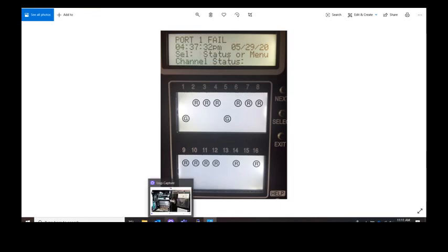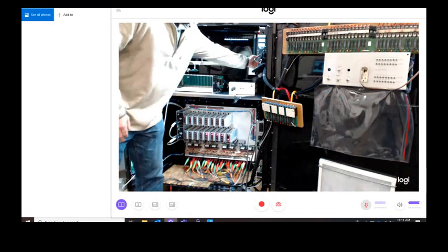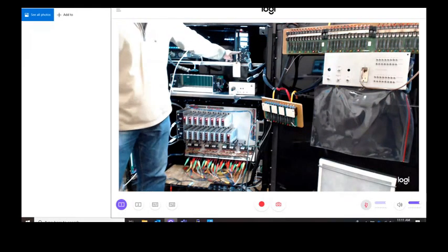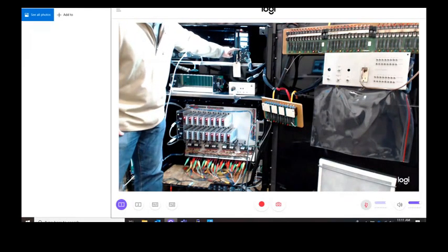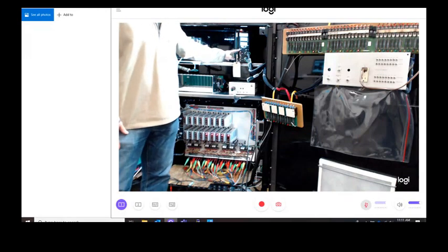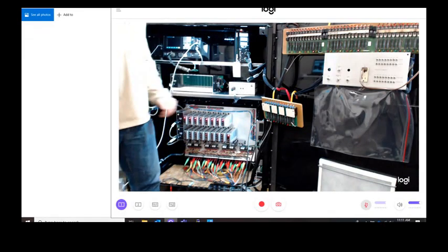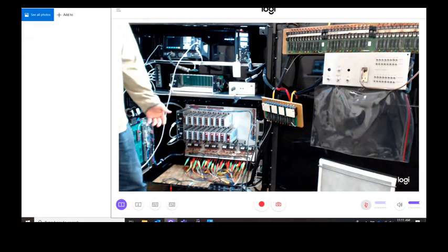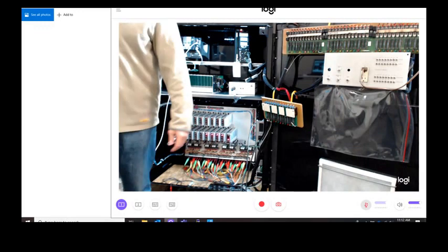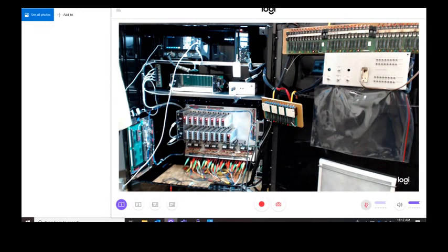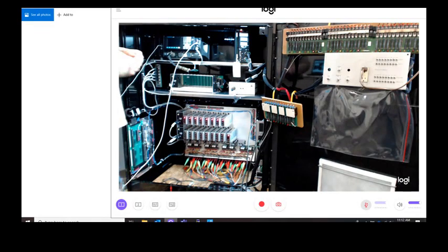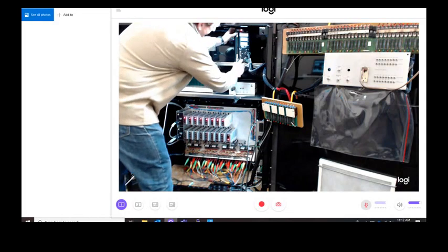But if I go to my camera, you'll notice with the cable off, it's hard to see, but I would have my transmit and receive lights flashing. They're completely dark. So if my cable was plugged in and those were dark, I would basically say, you know what, probably my MMU is bad and I got to change out my MMU. Or it's the MMU or it's the cable. So I would have to change out one of those other things. So what I'm gonna do is I'm just gonna put this guy back on.